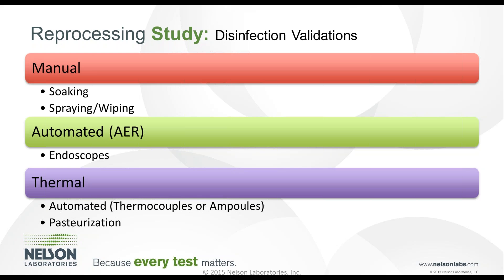Pasteurization is another method of disinfection utilizing just hot water. It's typically done in areas where chemicals are not readily available or where non-chemical-based disinfection is preferred. Canada is one market that typically prefers pasteurization, using water at approximately 70–75 degrees C and exposing the devices to that bath for approximately 30 minutes.